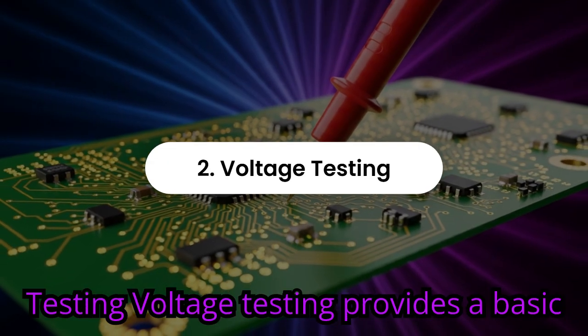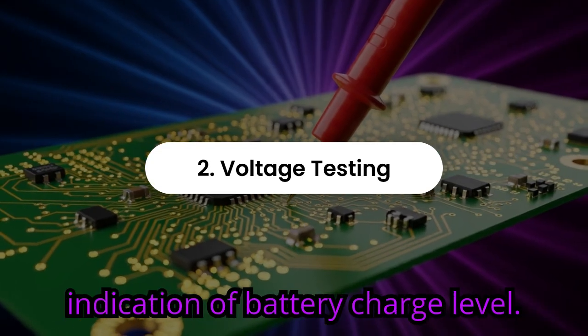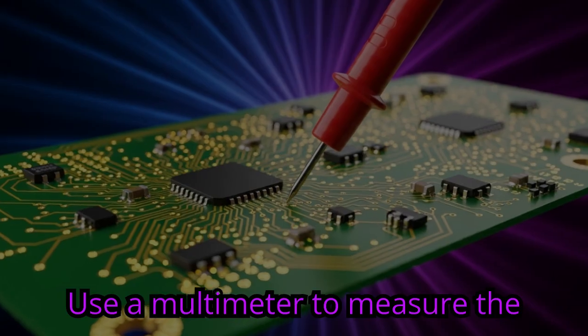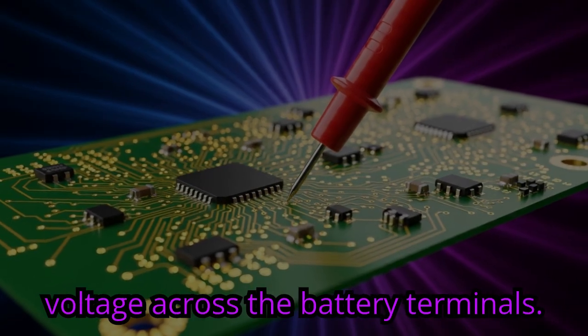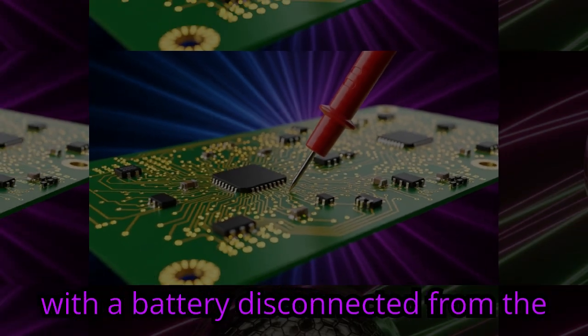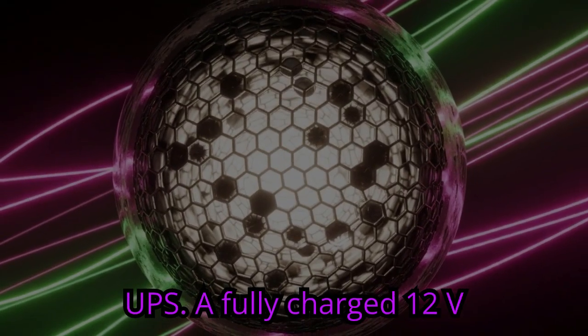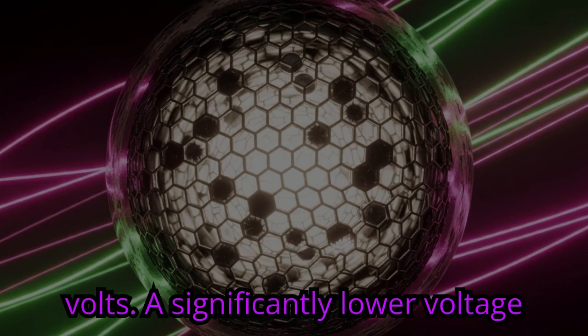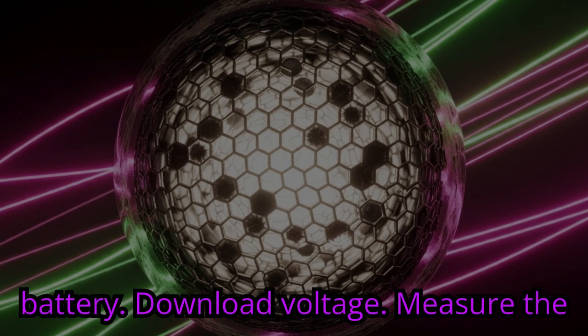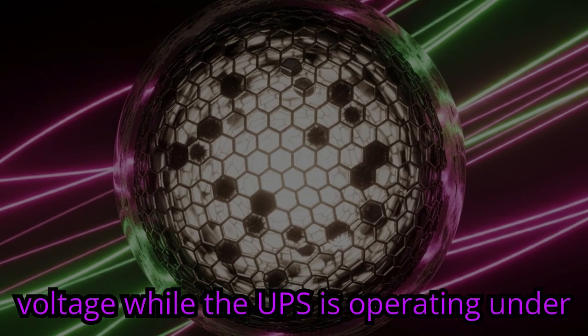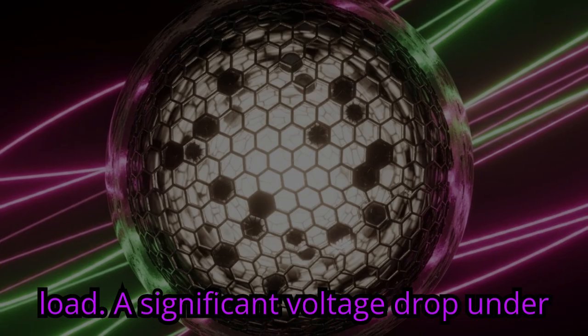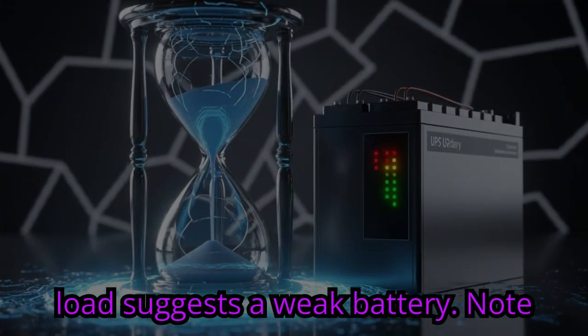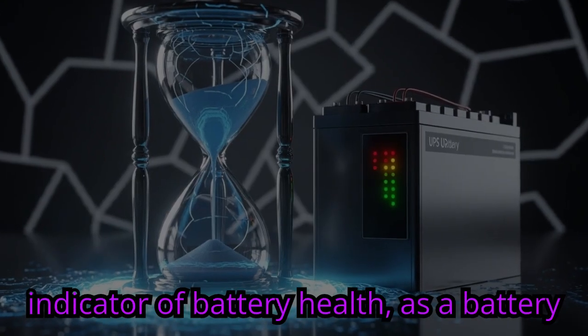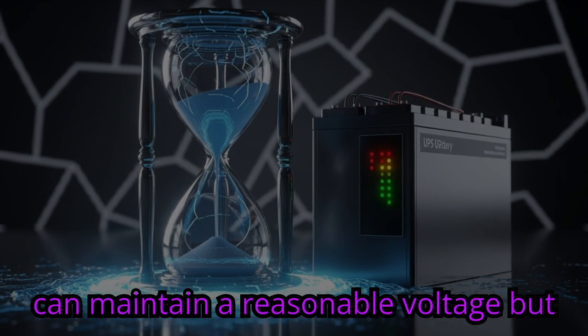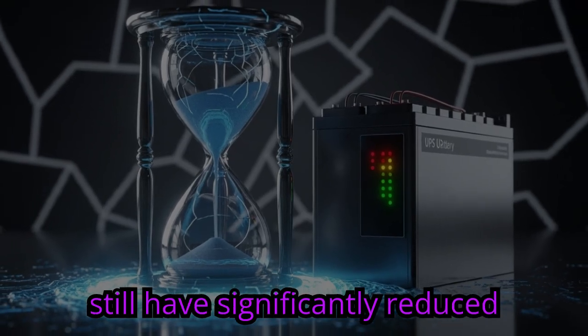2. Voltage testing. Voltage testing provides a basic indication of battery charge level. Use a multimeter to measure the voltage across the battery terminals. Open circuit voltage. Measure the voltage with a battery disconnected from the UPS. A fully charged 12V battery should read around 12.8 to 13.0 volts. A significantly lower voltage indicates a discharged or failing battery. On-load voltage. Measure the voltage while the UPS is operating under load. A significant voltage drop under load suggests a weak battery. Note: voltage testing alone is not a definitive indicator of battery health, as a battery can maintain a reasonable voltage but still have significantly reduced capacity.